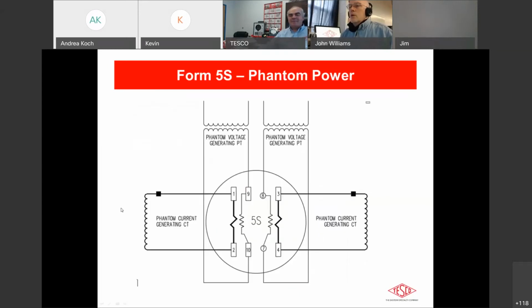Okay. So here we see we do a dual transformer arrangement for the potential. We have the two voltage coils, and we apply the voltage independently to each. Because we have that computer-driven output, we can make those two potential coils look like a delta service, in this case kind of an open delta service. And then the two current transformers on the current elements. With this arrangement we can simulate a typical 3-wire 240 service, all the way up to a 240 or a 480 delta, with just this arrangement and some software.